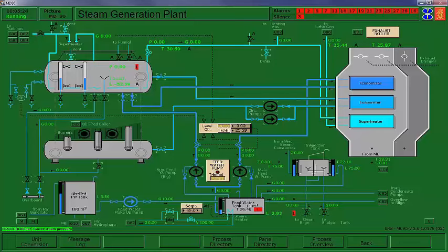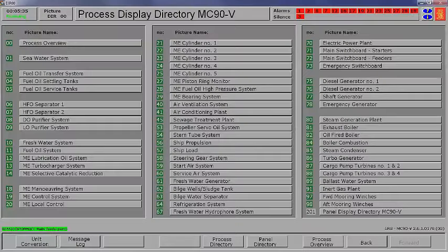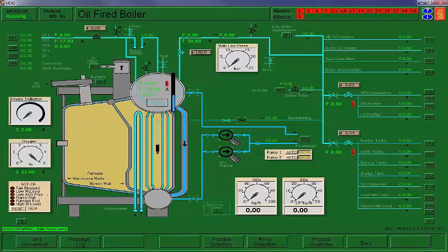Once the boiler water level starts coming down, you get below mid-drum, and go ahead and put it back on again. All right. So now that boiler is ready to go. We've got the proper valves open. Oh, by the way, too, on this steam drum, on the de-superheated steam drain, you would typically leave that open so that any water coming back, you would drain it out, and then once you've drained out your water, you're going to go ahead and close that.